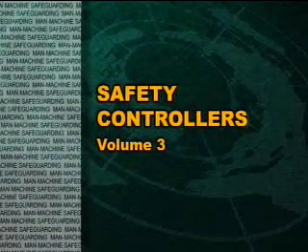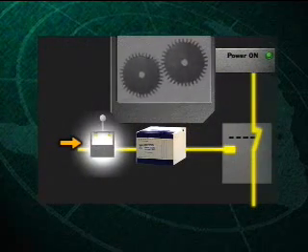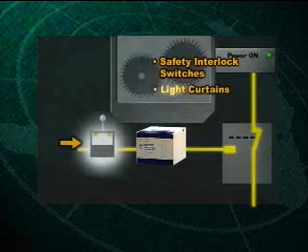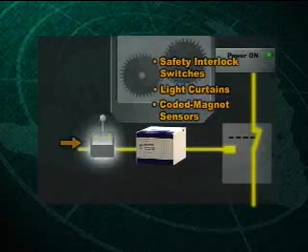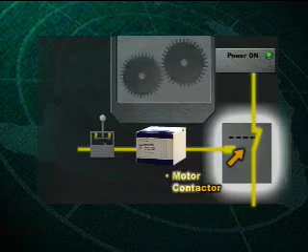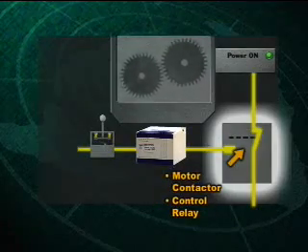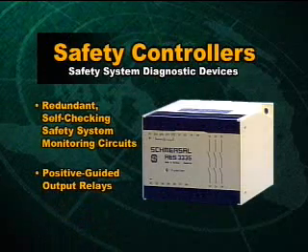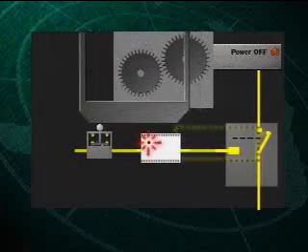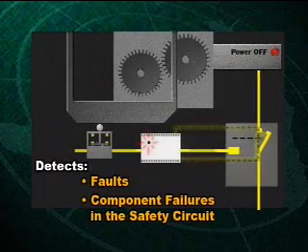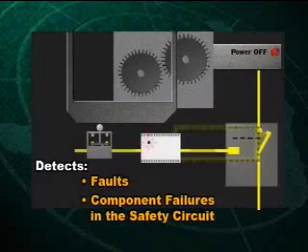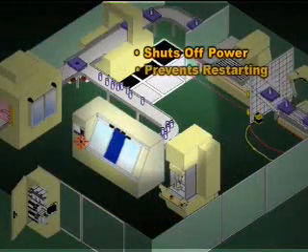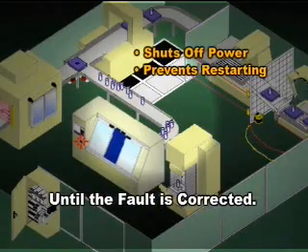Let's begin with a definition. Safety controllers are safety system components connected between machine guarding emergency stops or presence sensing devices — such as safety interlock switches, light curtains, or coded magnet sensors — and the machine's primary stop control element, such as a motor contactor or control relay. They contain redundant self-checking system monitoring circuits and positive guided output relays. Their purpose is to detect faults or component failures that may compromise safety system performance, and in such instances, shut off and prevent restarting of the machine until the fault has been corrected.